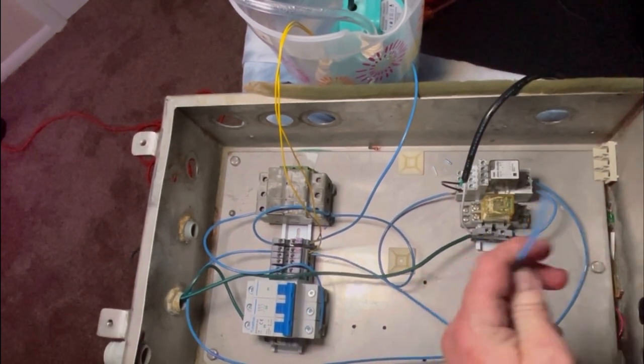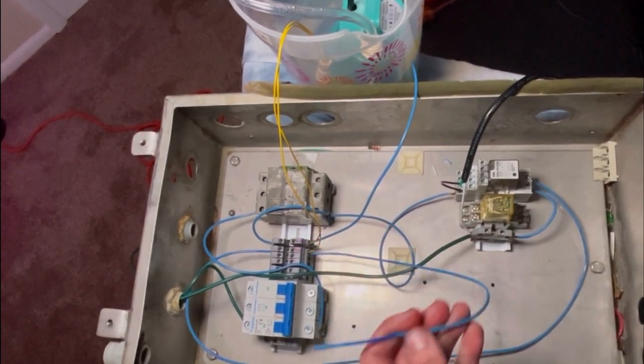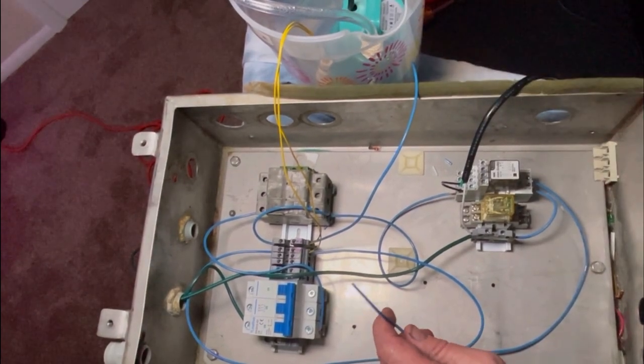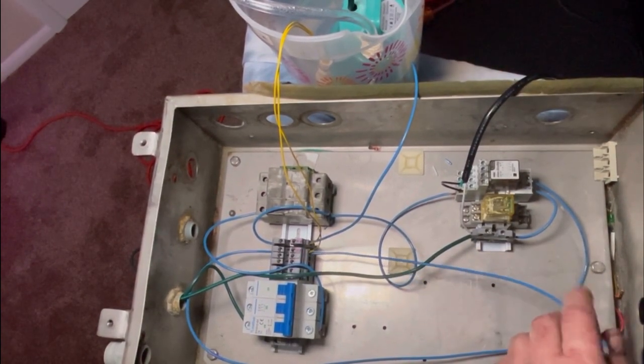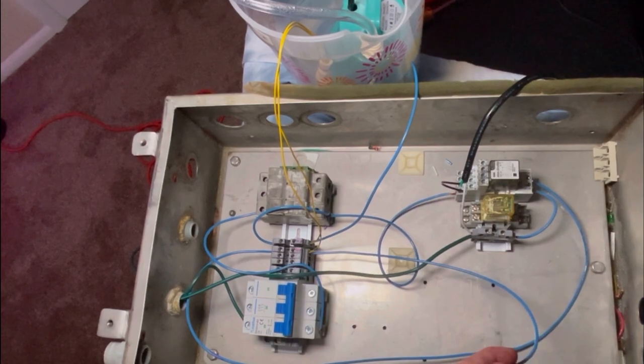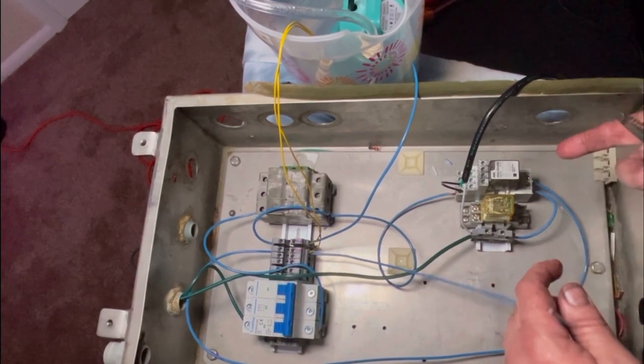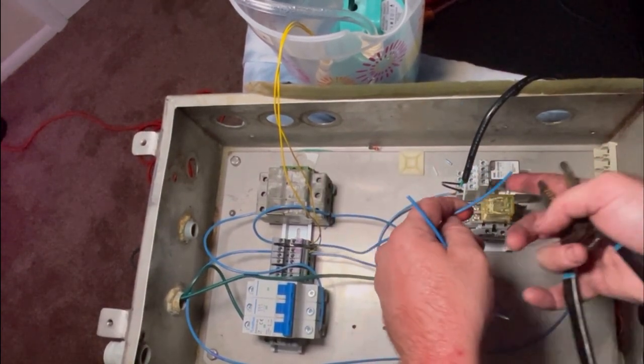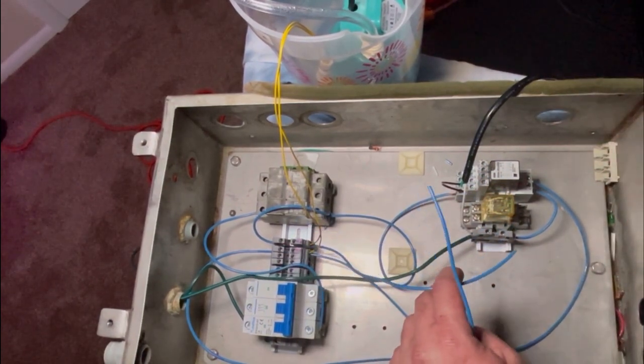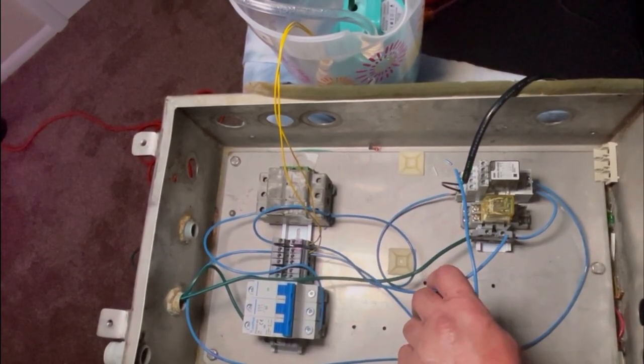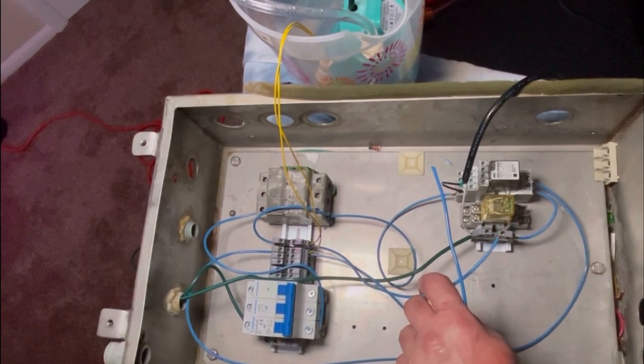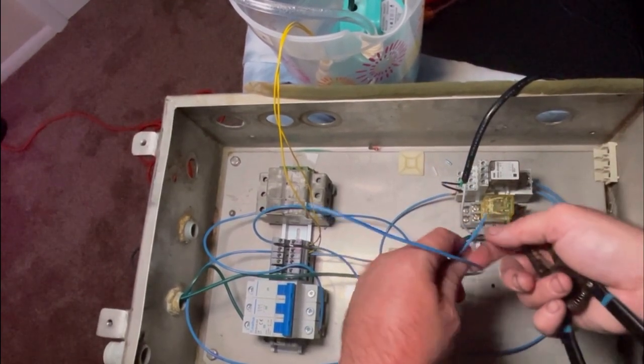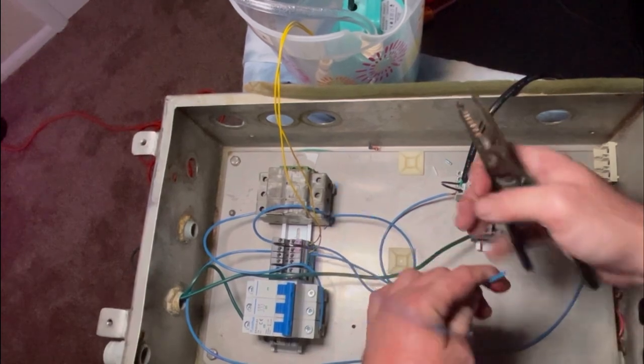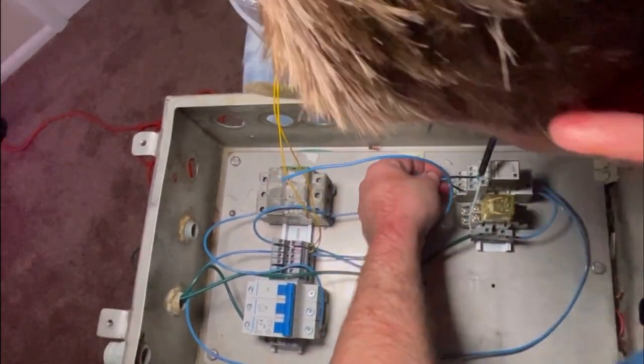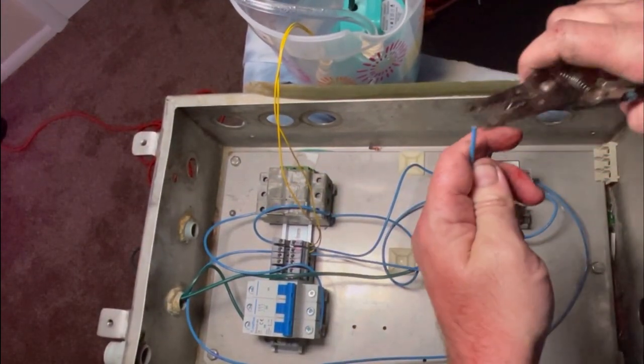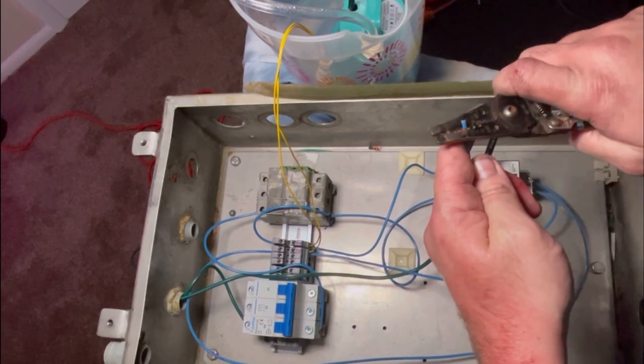So we're going to go 9, 5, and it really doesn't matter. It's just like an on-off switch. If you're using the normally open and the normally closed, then the polarity and which terminal goes to where is important on the relay. So we'll do it the right way. The incoming side is going to go to the common relay contact, which is 9. This one's going to 5. Again, I know this isn't clean.